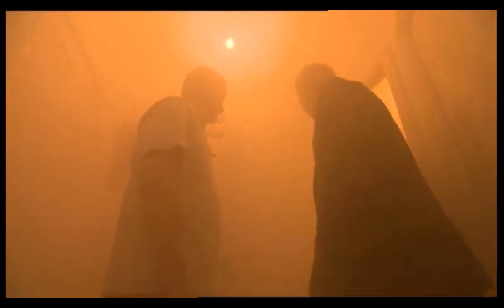Even though we've got a sealant round the bottom of there, it's through the duct at the bottom of the pan. To the bottom, yes. That's straight through from the kitchen. There's no break there at all. No. There's no fire protection. You might as well not have a fire door. Yeah, pointless. The smoke in this test isn't toxic, but smoke from a real house fire is.